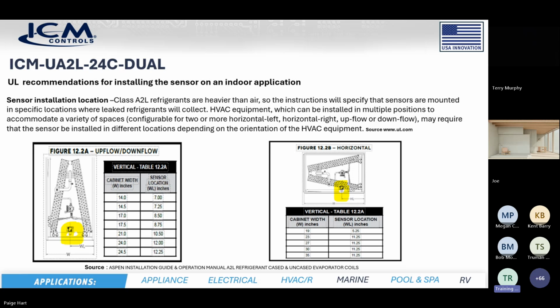So when they come in, if you ever have a new system put in, hopefully it will come with its own mitigation system by the OEM, which we also supply. But if you have a repair guy come in and he replaces just the A coil in your air conditioning unit, then he's going to have to put in a mitigation system if you didn't have one. So he's going to buy one of our boards, hopefully, and he's going to have the sensor included in the kit. So the sensor comes included in the kit that you buy with the UA2L-24C-DUAL. And so we looked up the UL recommendations. Again, every system is going to be a little different, so I can't tell you exactly where the sensor is going to go in every single system. But in general, the instructions will specify the sensors are mounted in locations where leaked refrigerants will collect.